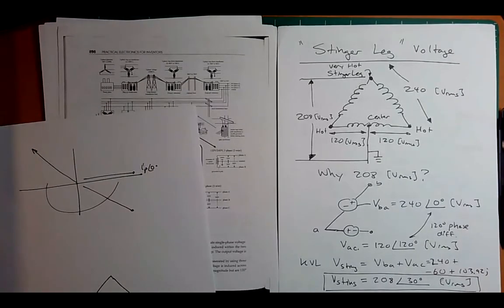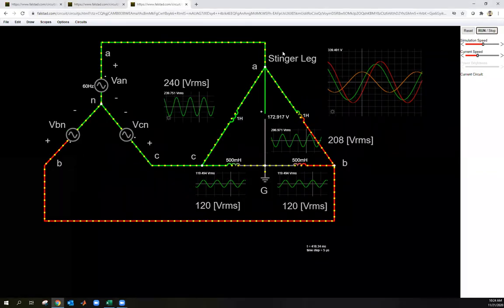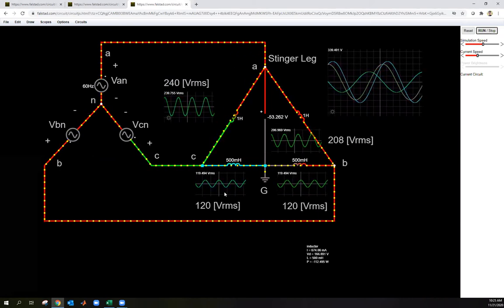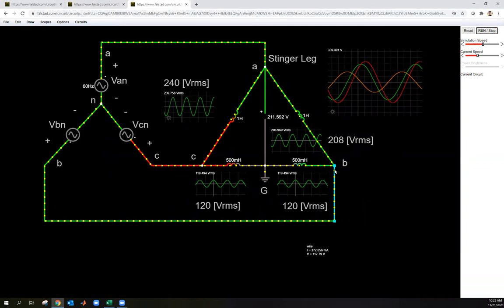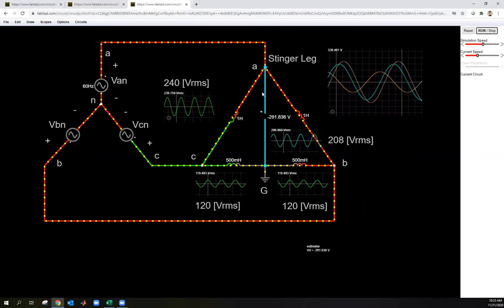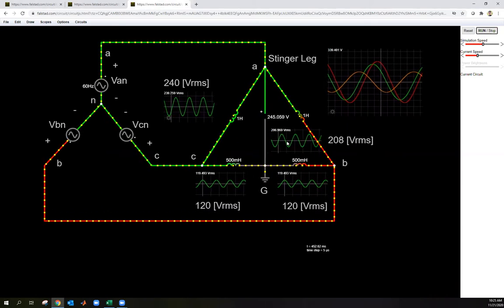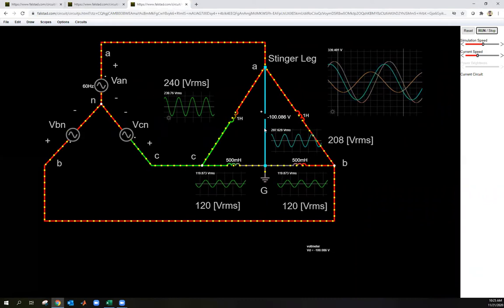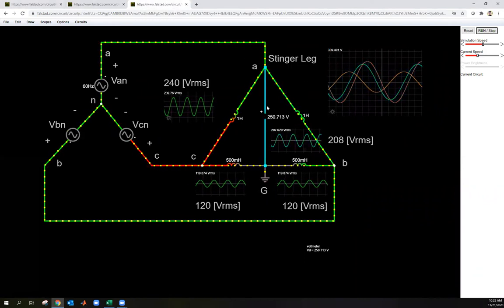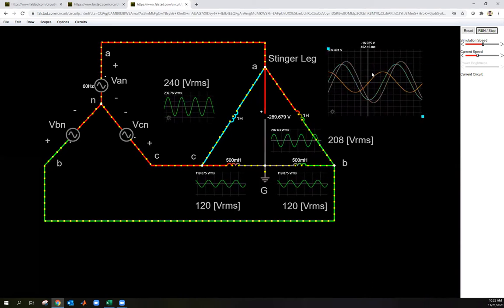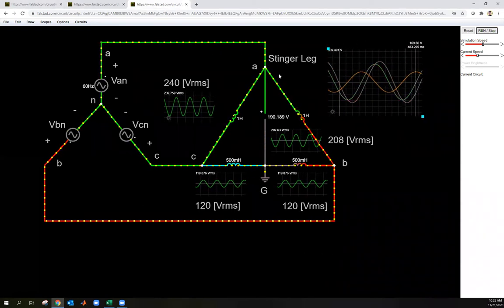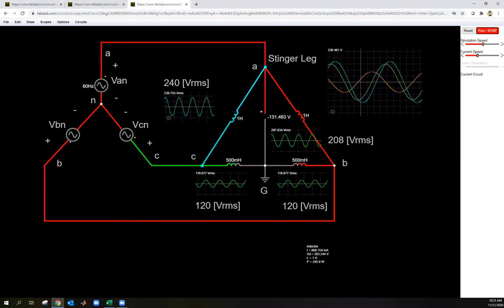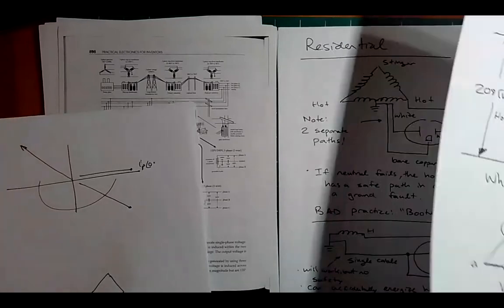In the simulation showing the stinger leg: the secondary of a transformer has 240 V across one winding, 120 V from ground to each hot. A probe from the third phase point to ground shows 208 V RMS. Plotting all three, you can see the 208 V voltage is leading the 240 V by 30 degrees, with the 120 V also visible. This is an example of a stinger leg in a residential setting.